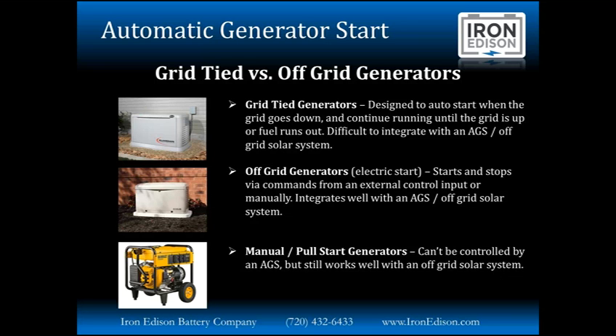These generators don't have that transfer switch or the grid current sensing features. They basically have a remote start-stop logic input, and they're looking for a command to start up and to shut down. And those commands will be sent to it by an AGS like the Schneider AGS or AGSs from other manufacturers. These, again, are the best solution for an off-grid or solar system, or any system that's using an AGS to control the generator.